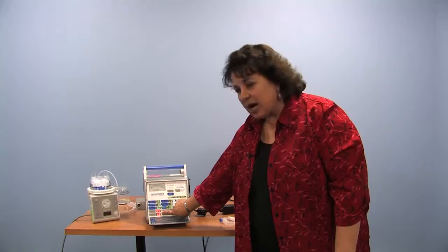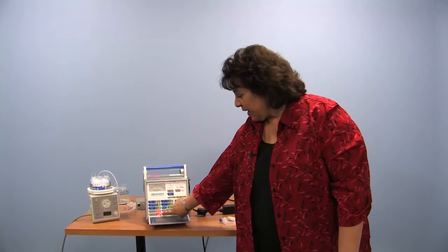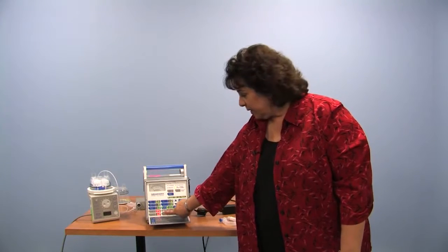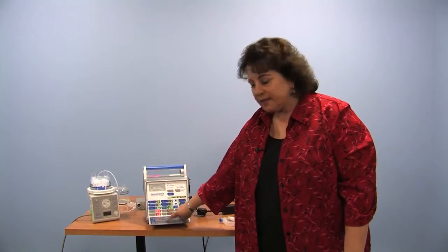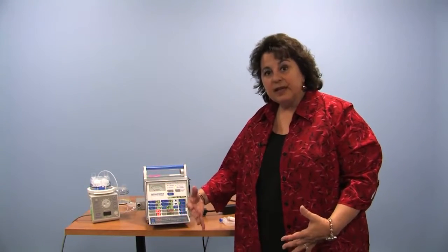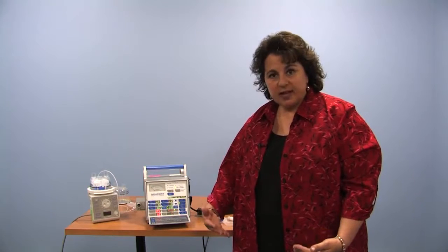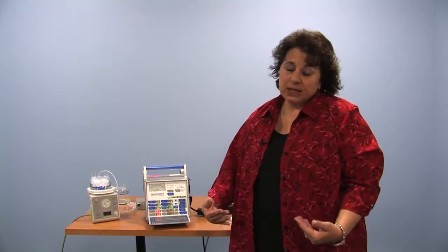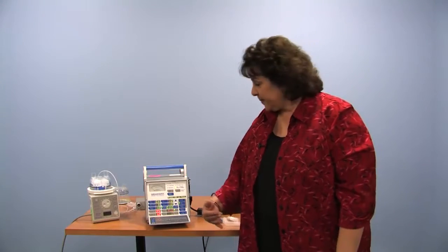In the red here, red sort of signifies an alert. We have a high pressure alarm, 35 centimeters of water. This is currently set at that. That means that the pressure in the child's lungs will not exceed 35. Even if they cough against it, at 35 the machine will dump any excess pressure and volume and let another breath cycle happen. That will signal an audible alarm and a visual alarm. You will see and hear it, and it will call your attention to the fact that perhaps they may need to have their tracheal tube suctioned.